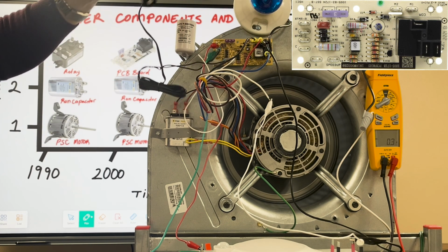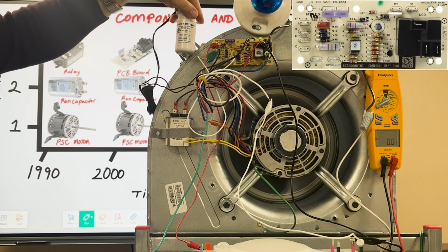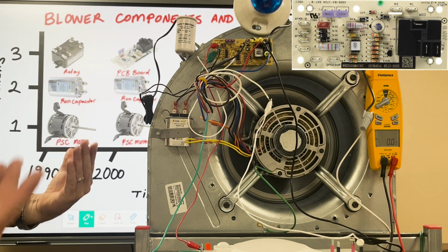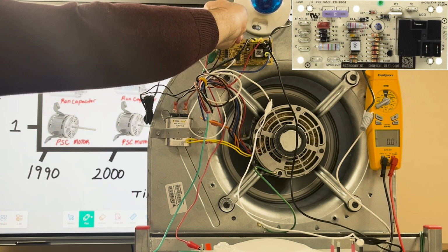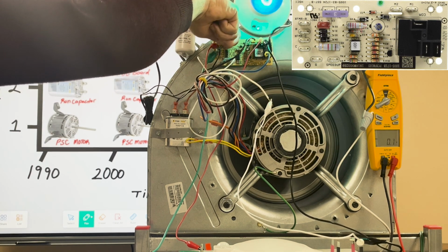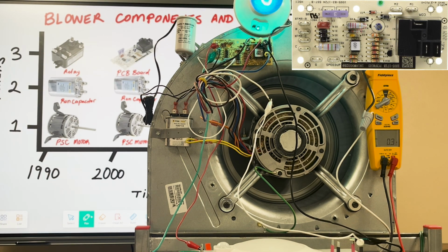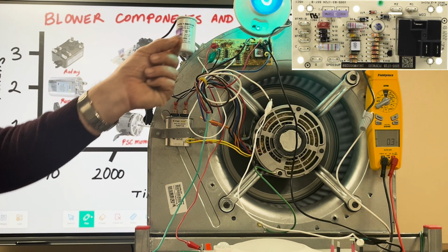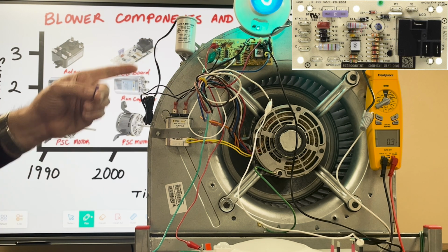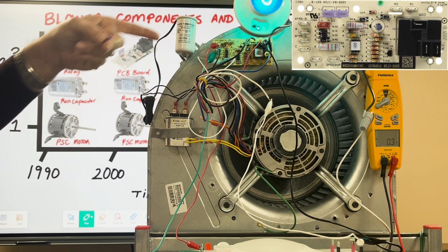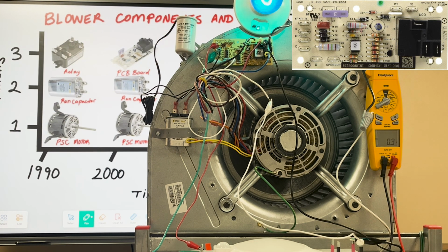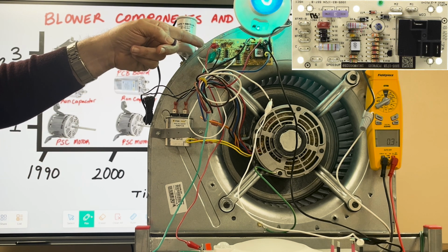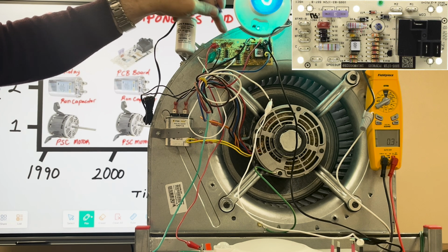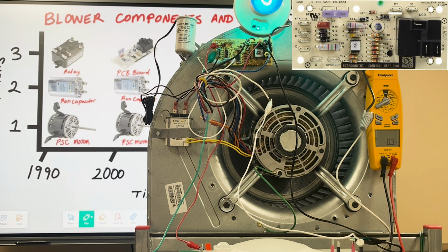So let's look at another way we can do this. I'm going to go ahead and put this back in here. Let's say my fuse was open. Say my fuse was blown. Okay, I can just simply take my fuse out. Same thing. Now, anytime you have a blown fuse, you'll have 24 volts going into the board, but you will not have 24 volts coming out on the R terminal. Okay, you'll have 24 volts going into your board, but if your fuse is blown, it's open, and if it's open, then you will not have 24 volts back out on R.